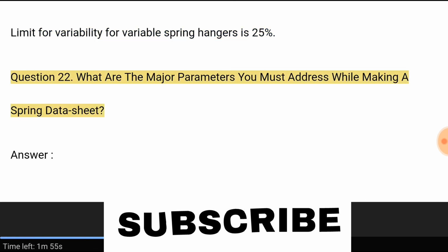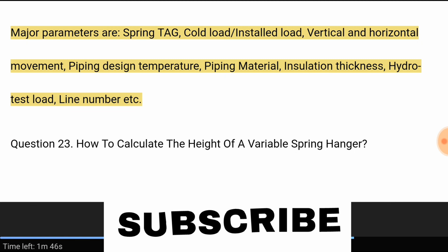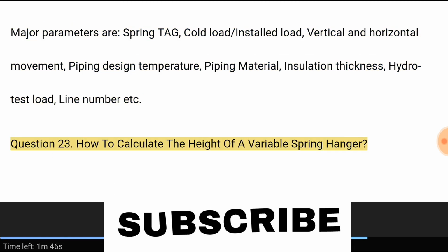Question 22. What are the major parameters you must address while making a spring data sheet? Answer. Major parameters are spring tag, cold load, installed load, vertical and horizontal movement, piping design temperature, piping material, insulation thickness, hydro test load, line number etc.